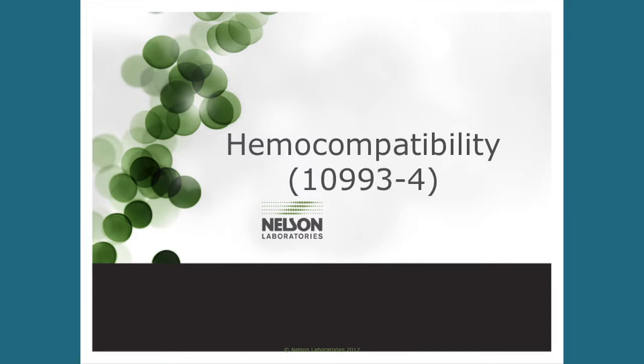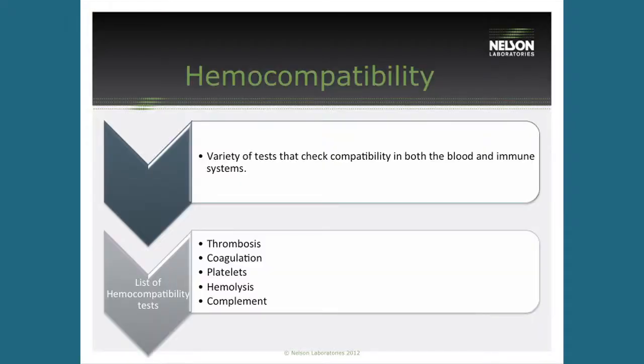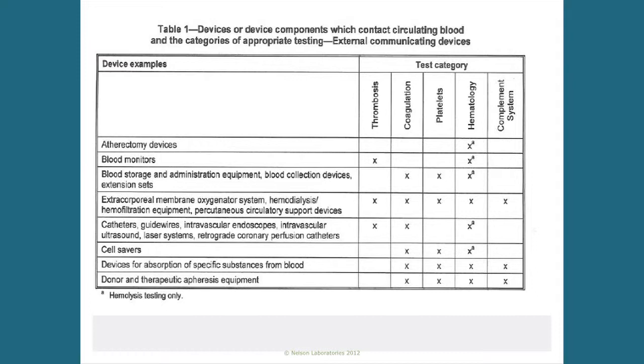Next we're going to talk about hemocompatibility. In ISO 10993-4, we have a toolbox of tests that we can use to evaluate hemocompatibility. Those tests are thrombosis, coagulation, platelets, hemolysis, and complement activation. You don't have to do all those tests for every device, but those are the toolbox we have to evaluate hemocompatibility.